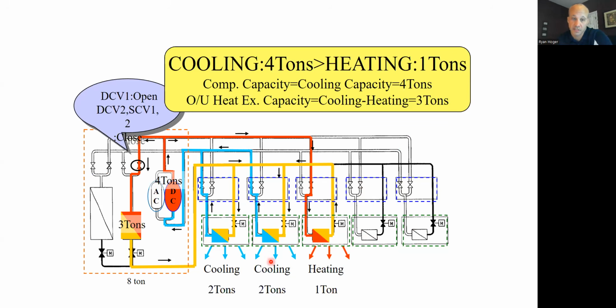That's not what I'm going to do in this case. I'm going to run my unit in whatever the higher demand is, cooling in this case. So the outdoor unit goes to cooling mode, meaning he's going to send cool refrigerant on this yellow pipe over here to these zones to pick up heat. When I pick up that heat, it's going to go back through the compressor. And instead of going outside to reject the heat, some of it's going to go inside and reject the heat over here. And some of it's going to go outside. So I've got 4 tons of cooling. So I have 4 tons of evaporator coil surface, if you will.